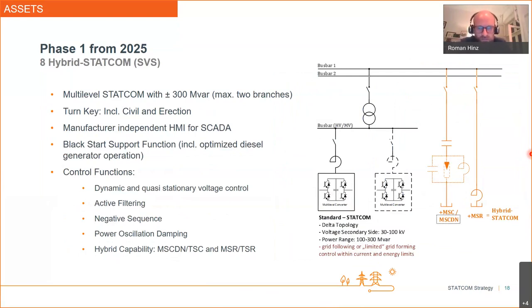But we are also aware that every manufacturer has their own specific design, and we have to consider this. But what we know is that the standard topology of a STATCOM is, for example, a delta topology. So it's not like a B6 bridge, or a star topology. Usually we use delta topologies, and there are some advantages, for example, for negative sequence control. This is one of the reasons, and also some others.